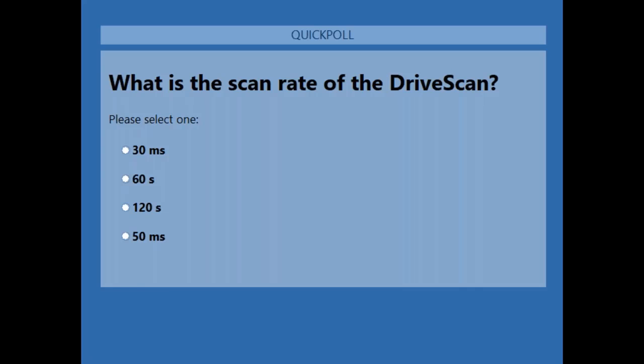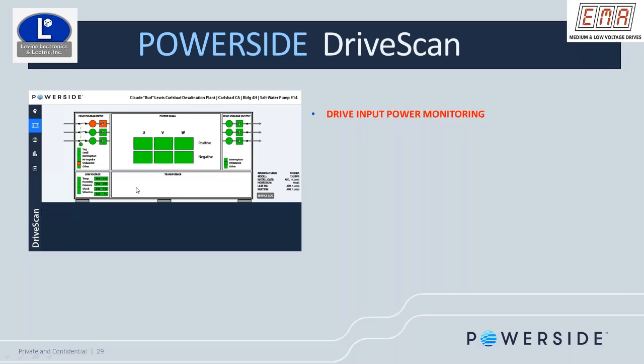In this example, if we're missing a single phase in our cloud-based software, we would see this turn red. That means we're missing a single phase, and we can address that, drill in, and see the actual voltage and the graphs coming in. We'll also see unbalance, because if we lose a single phase, we'll have an imbalance situation. This is on a Toshiba T300 MVI drive.